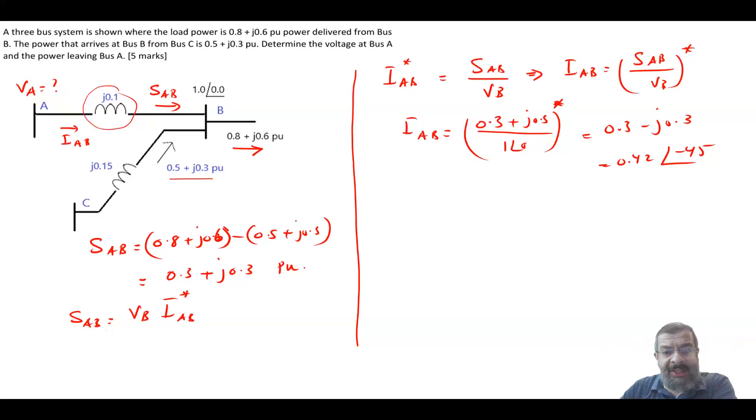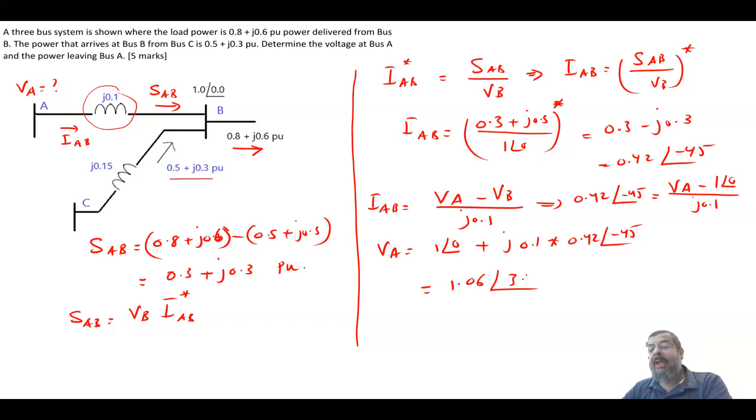So that is the current that enters bus B, but it's the same current that is leaving bus A because there is no shunt element. Now, this current IAB is equal to VA minus VB divided by the impedance between them, which is j0.1. We know everything except VA. So 0.42 angle of minus 45 is equal to VA minus one angle of zero divided by j0.1. So your VA is equal to one angle of zero plus j0.1 times 0.42 angle of minus 45. And this will give me a voltage equal to 1.06 angle of 3.24.